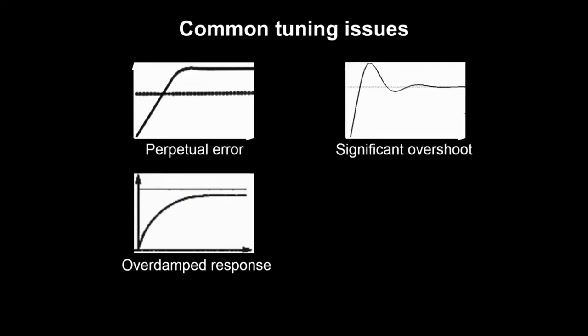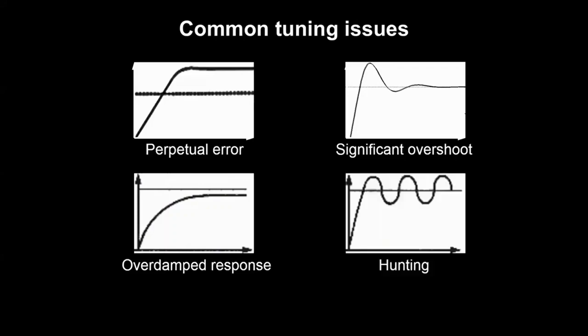We can have a quicker control loop, but maybe now we're overshooting a little bit. And in systems where we're susceptible to, say, high pressure or temperature changes, like within a duct, that may become an issue. We may damage equipment. And we may have what's called hunting or cycling.